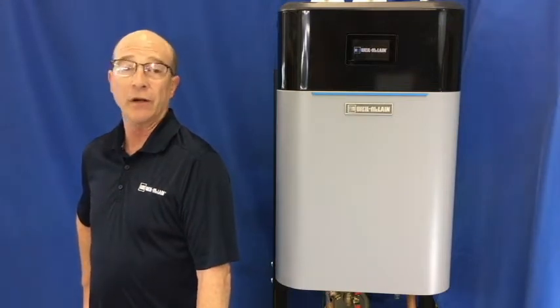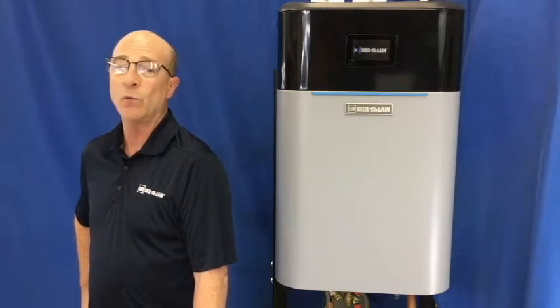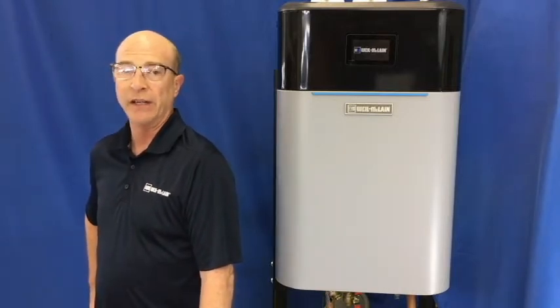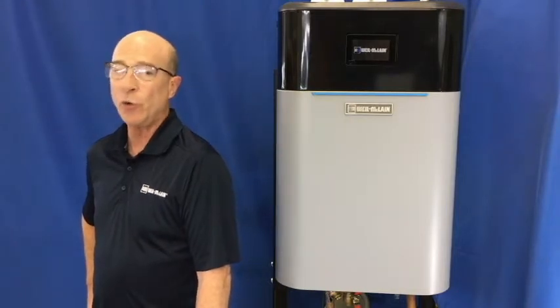The boiler can be operating normally for space heating, but if the domestic hot water heat exchanger is building up lime scale, the unit cannot get the heat to the domestic water and the boiler will shut down or overheat.